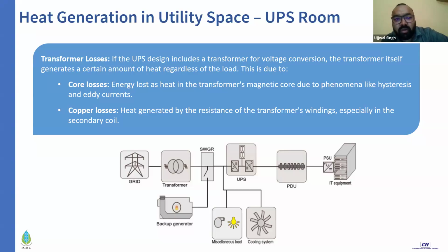Now we'll start with the transformer losses. Many of you will understand that there are two kinds of transformers used in data centers. Earlier, we normally had oil-cooled transformers placed outside the data center building in the open area, naturally cooled by the airflow. But with the modularity coming up in data centers, dry type transformers have started getting included, and these dry type transformers are generally kept in your LT panel or HT panel rooms. They contribute minimally, but they still contribute to the heat load in data centers.